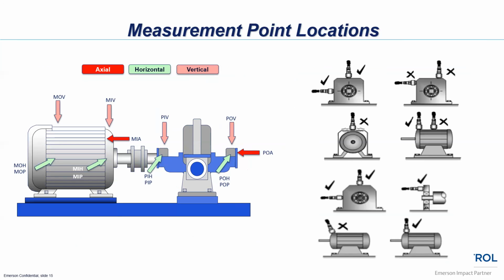More measurement point locations. Again, as I was referencing here, this is a horizontal point where we would get the horizontal point on that fan bearing, but we don't have to move up to the vertical or to the axial anymore, because we can get them all just from this one position here.